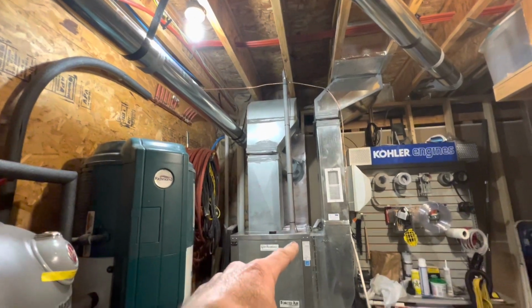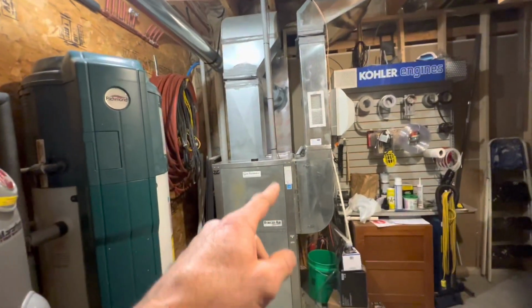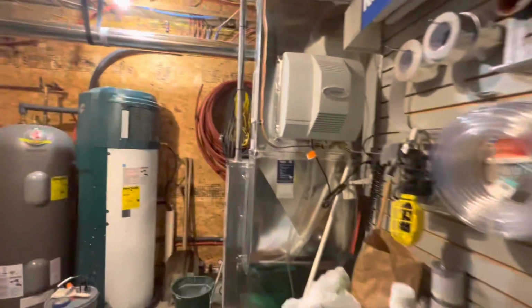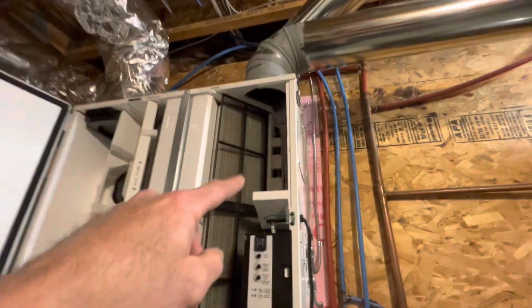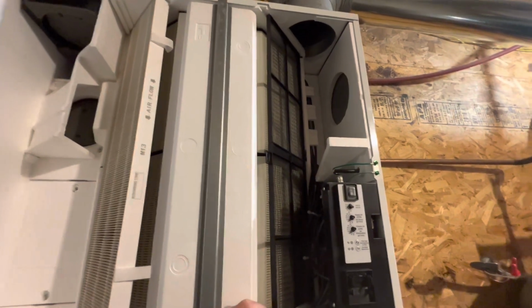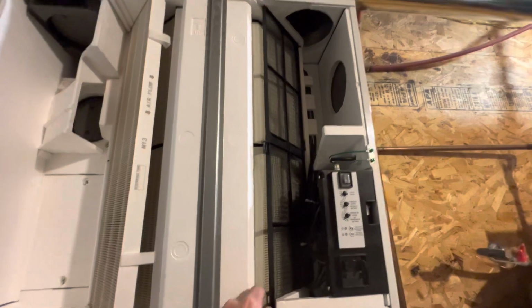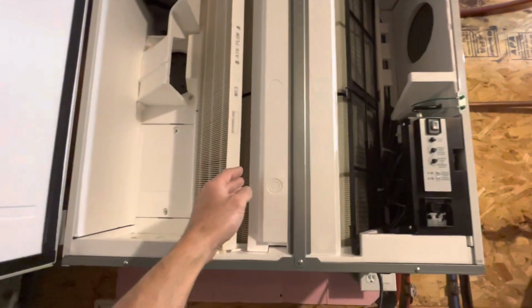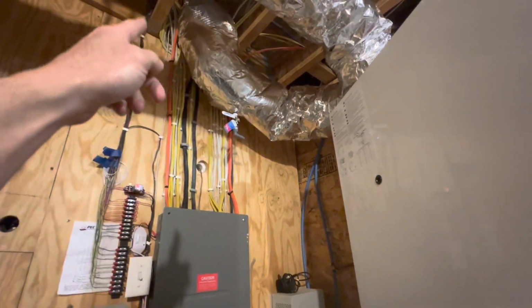At the same time, for the stale air going out, exhausting, I have it coming from that line, which, if we go on the outside of that wall, I have it coming from that vent, following that stud cavity, going up through that ductwork, through this filter. It doesn't have to be as good of a filter because that's just the air going out. Essentially the indoor air should be clean anyway. Through the core heat exchanger to this side of the unit, out this ductwork and outside.